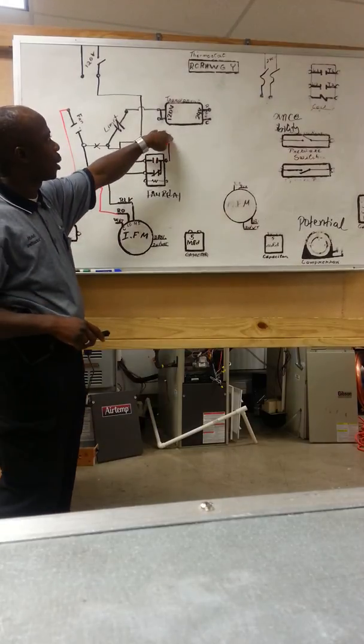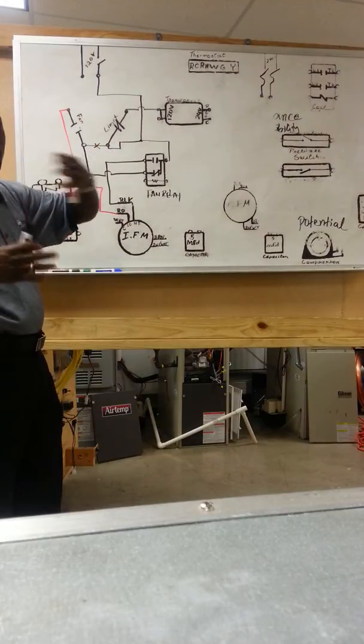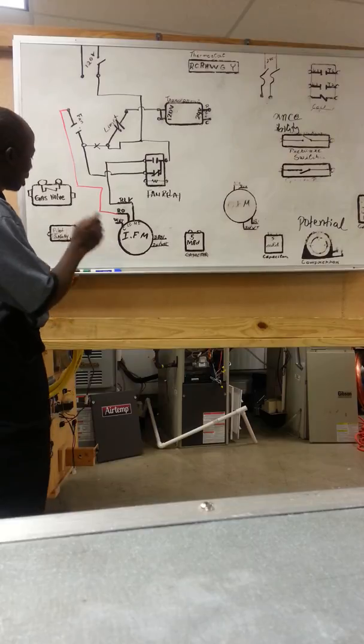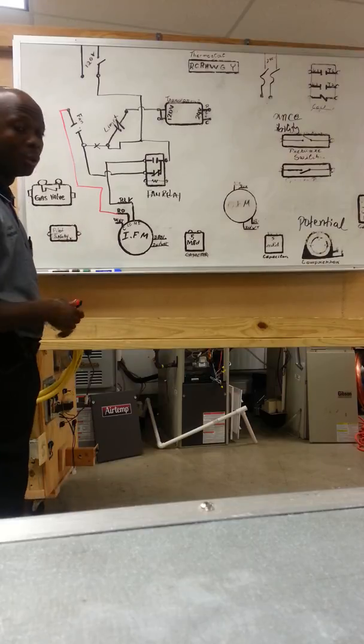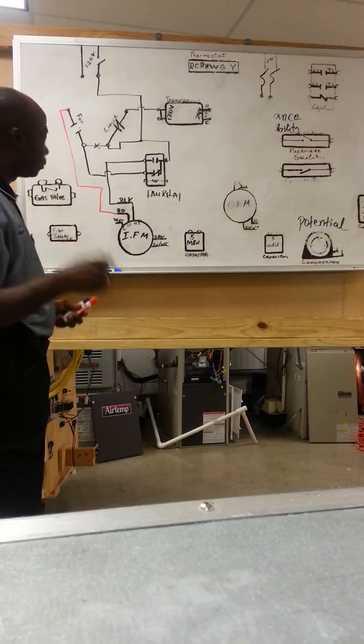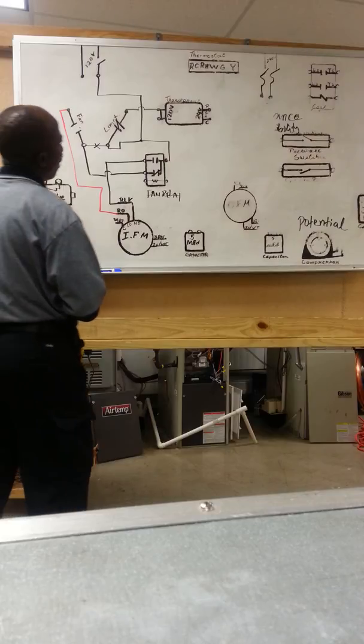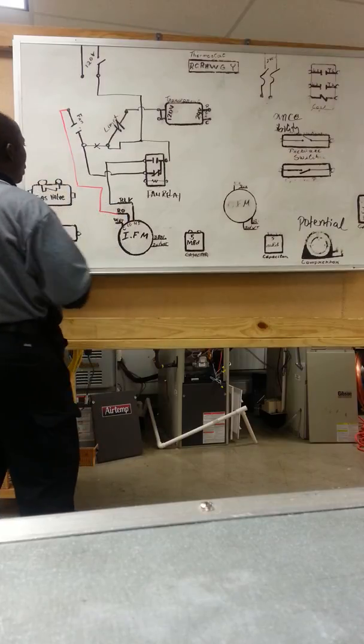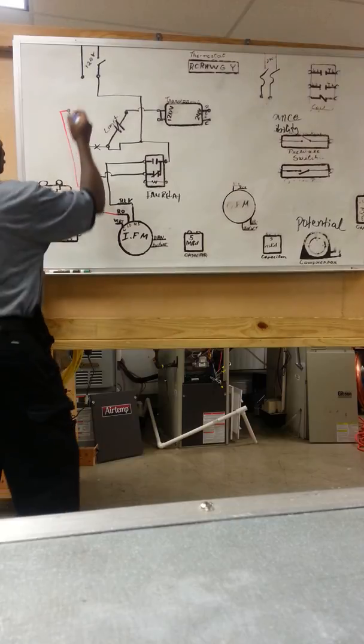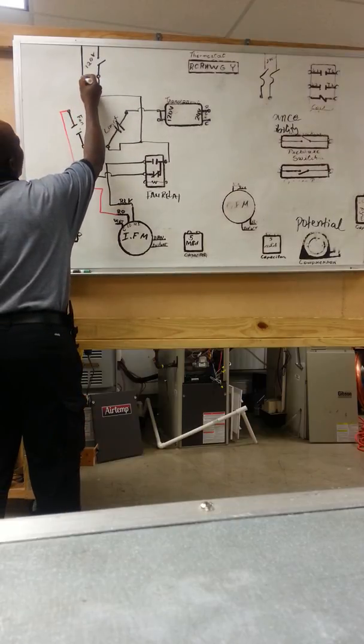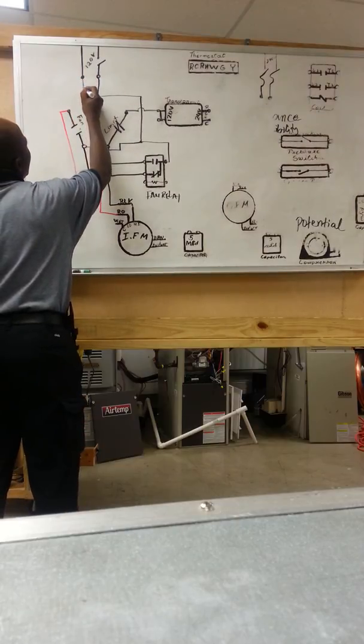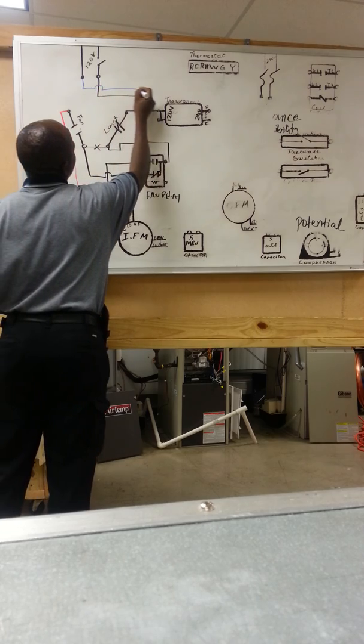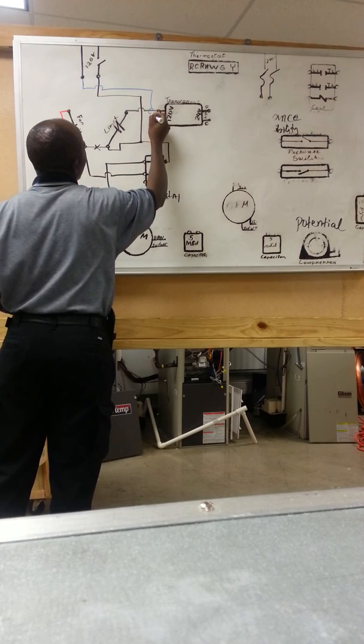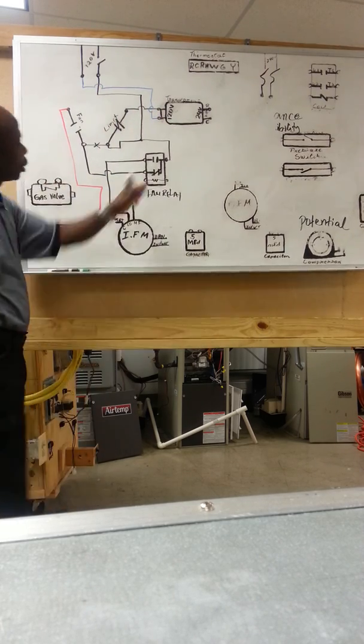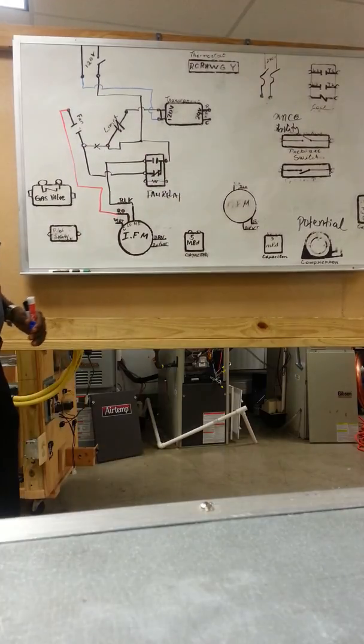This transformer is not working yet because you need to have a neutral to have a complete polarity. So right now that's not working. I'm going to be using blue for white. So now what do I have to do? Let me complete this circuit coming in with 120 volts. I'm going to get a neutral wire coming from here, which is going to be white. And that's going to jump out. Transformer has 120 volt right now going to the transformer.